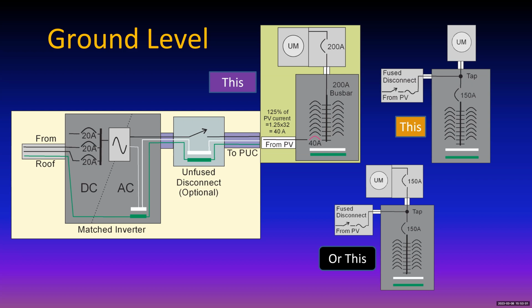Let's say you have 150 amps coming in from the utility, that's your maximum amount, then you can't try to send more than 150 amps back to the utility. And I had one just a day or two ago. There's a huge system of 40,000 watts that had a 200 amp breaker connecting in instead of a 40 amp breaker, and that was into a 200 amp service. So the actual output of the system was around 160, but still, it's pretty close. But it couldn't go much higher than that because you'd have to have a service change to a bigger service, and the utility may or may not go along with that.